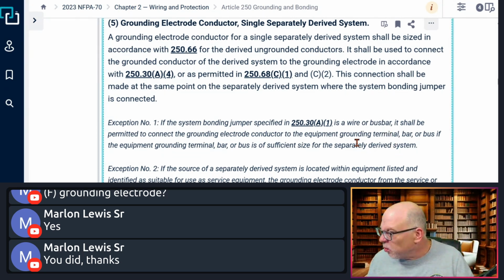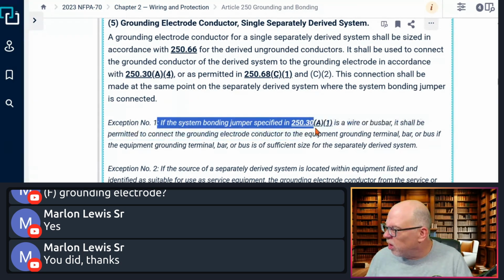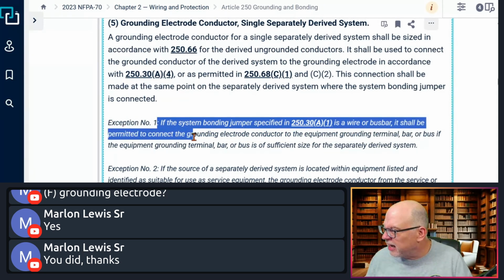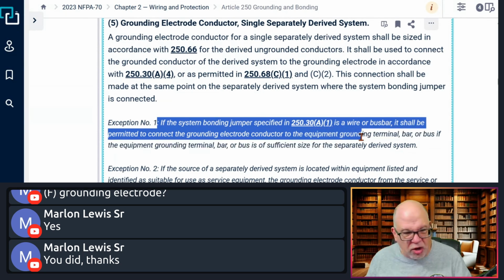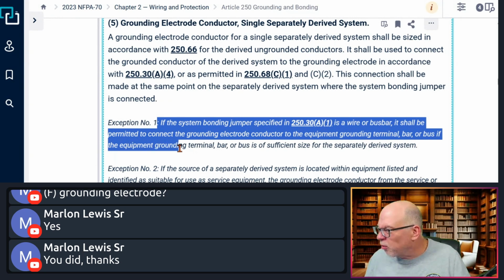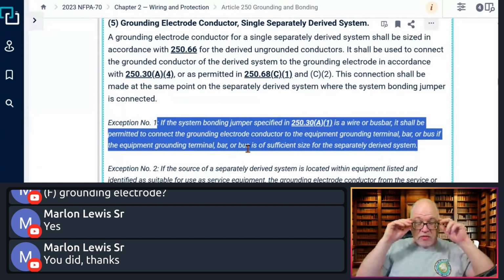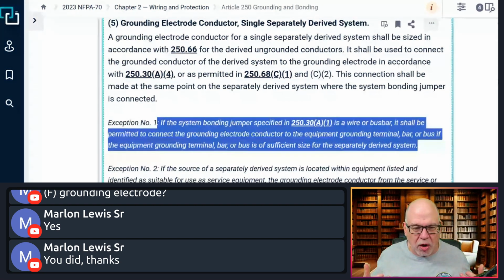Hold on, let me read the whole thing because I broke it up. Except if the system bonding jumper specified in 250.30(A)(1) is a wire or bus bar, it shall be permitted to connect the grounding electrode conductor to the equipment grounding terminal, bar, or bus, if the equipment grounding terminal bar or bus is of sufficient size for the separately derived system. So there's an adequately sized bus bar with enough terminations on it.